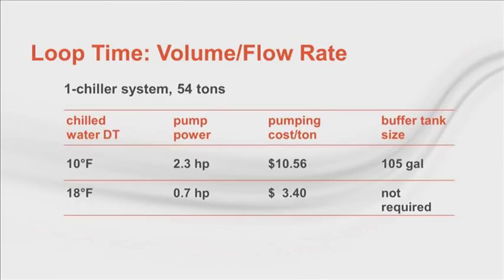As we showed in the 2004 program, the need for a buffer tank can be minimized or even eliminated by using a low flow design. Here's one example. A 50-ton single chiller constant flow system. Using a 10-degree DeltaT costs about $10 per ton of cooling and needs about 100 gallons of buffer tank for minimum loop time. The equivalent system with an 18-degree DeltaT uses a third of the cost for pumping and doesn't need a buffer tank. That's all the design options we'll cover today for constant flow systems.